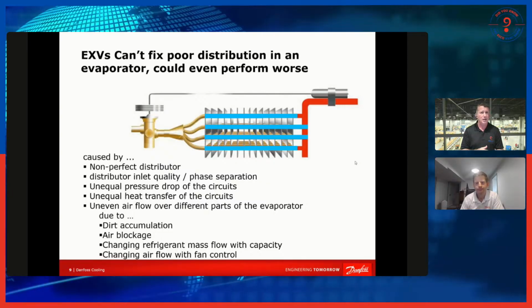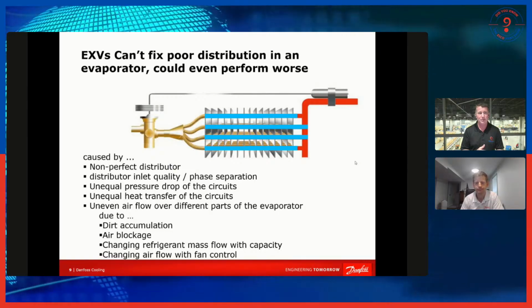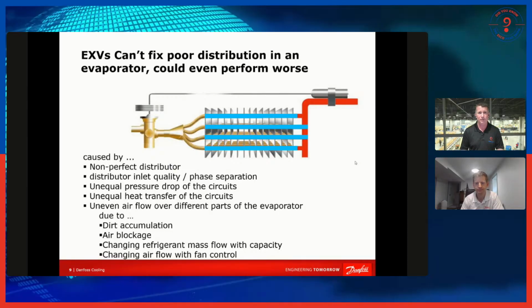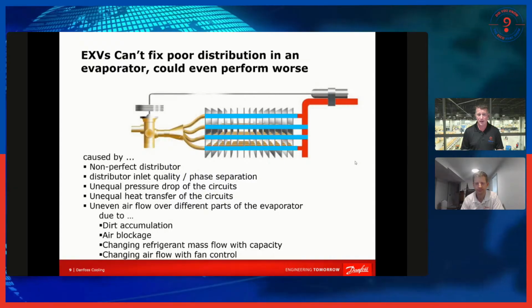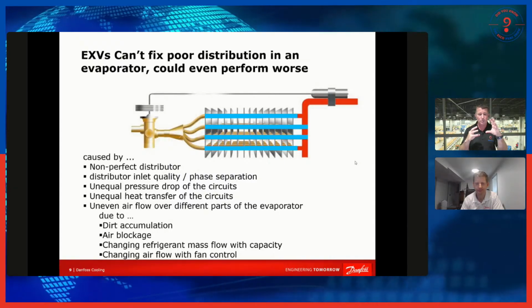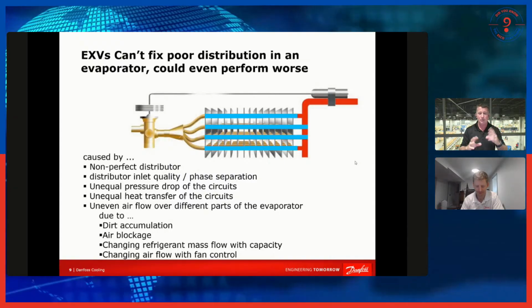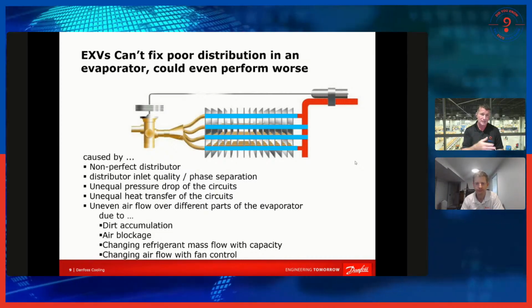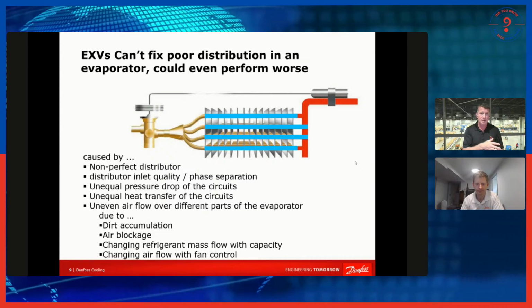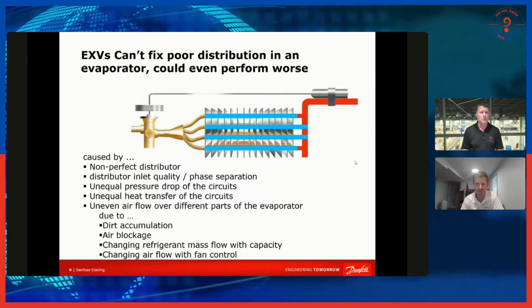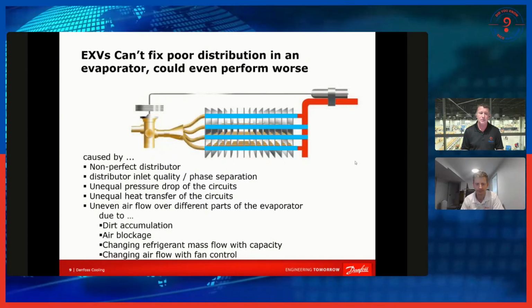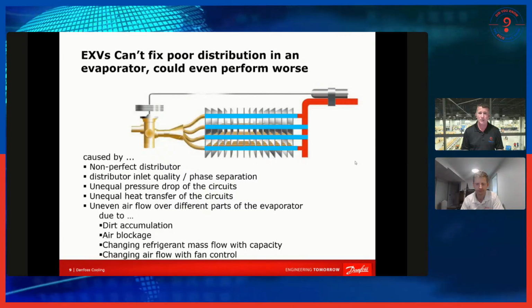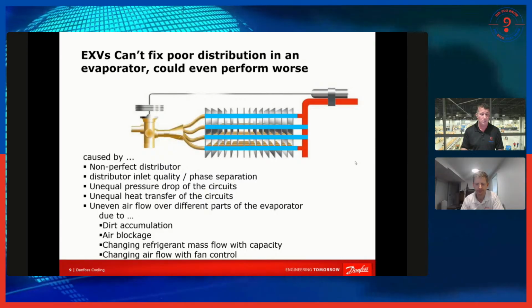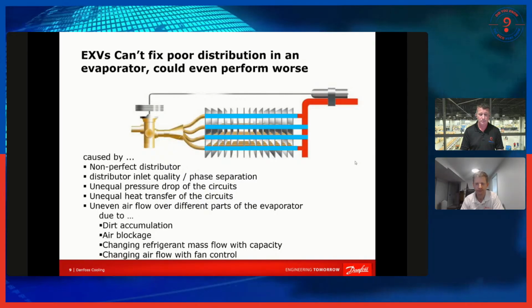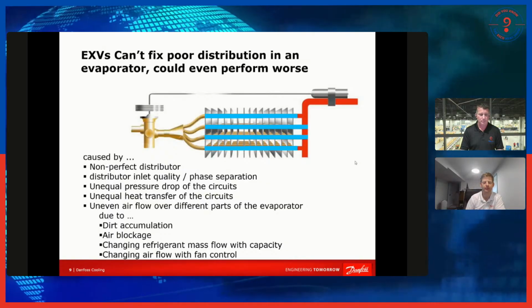One of the things we have to be very aware of when we're using electronic expansion valves is that when we're reducing that airflow, it's really going to start reducing capacity of the system, because that EXV is going to be so finely tuning that refrigerant flow along the way. We still have that same function in thermostatic expansion, but once we get into electronic expansion, it's real critical to understand the airflow operation. And then when we move into inverters, it's a whole other story with our airflow. Yep, absolutely.